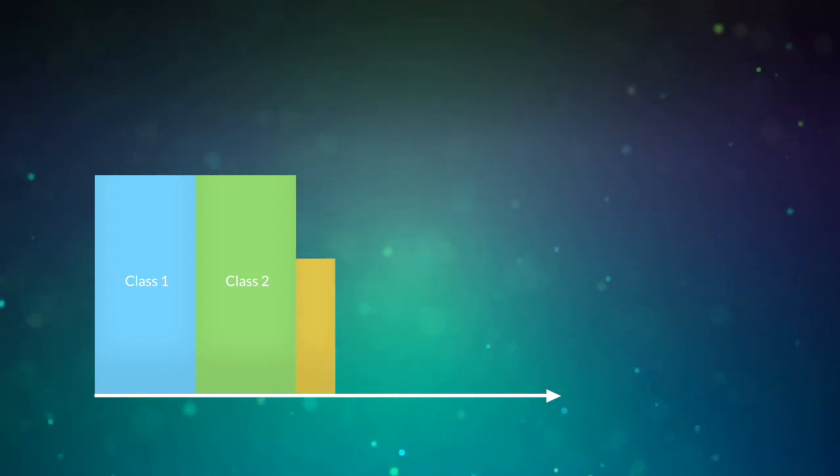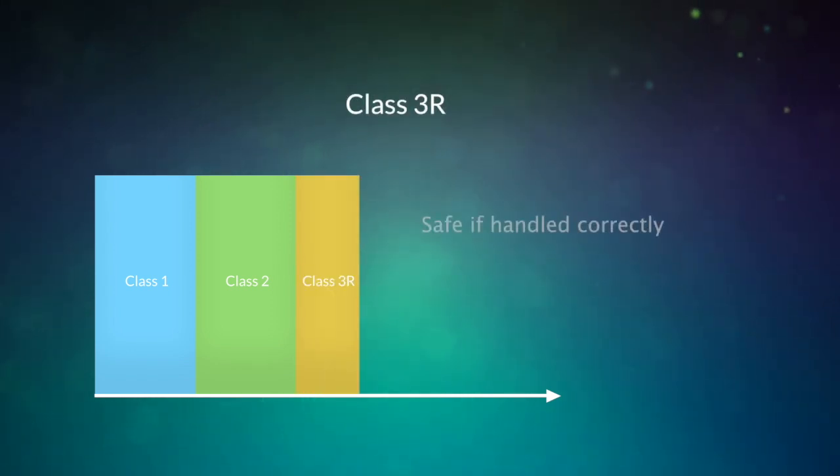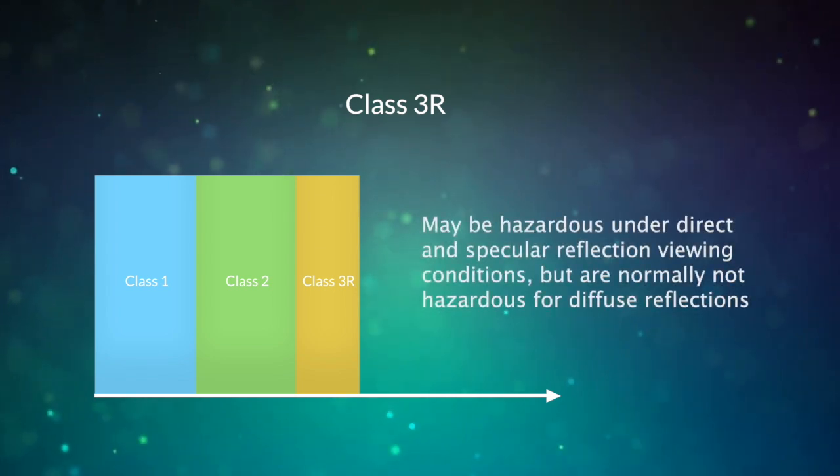Class 3R lasers are considered safe if handled correctly. For visible light, Class 3R lasers are limited to 5 milliwatts continuous emission. Class 3R lasers may be hazardous under direct and specular reflection viewing conditions but are not normally hazardous for diffuse reflections.